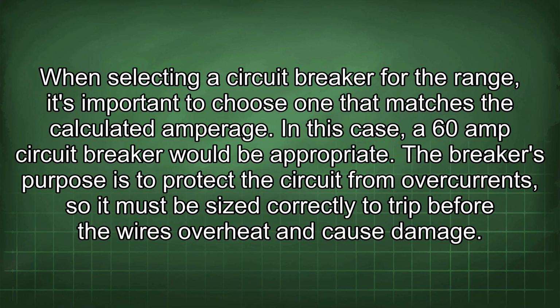When selecting a circuit breaker for the range, it's important to choose one that matches the calculated amperage. In this case, a 60 amp circuit breaker would be appropriate. The breaker's purpose is to protect the circuit from overcurrents, so it must be sized correctly to trip before the wires overheat and cause damage.